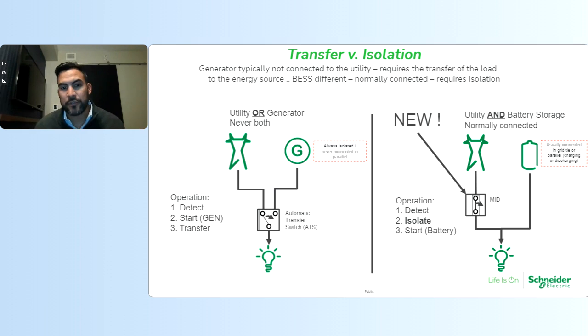It monitors voltage and frequency. Once it detects an outage, the electrically operated breaker in this device will open, safely disconnecting from the grid, signaling the energy storage system that, hey, we're now safely disconnected. You can change state from grid tied to grid forming.